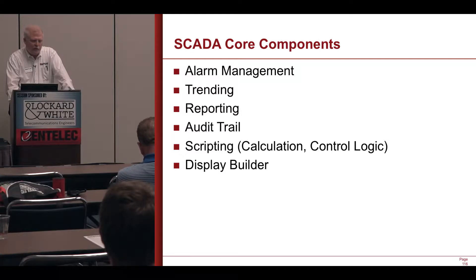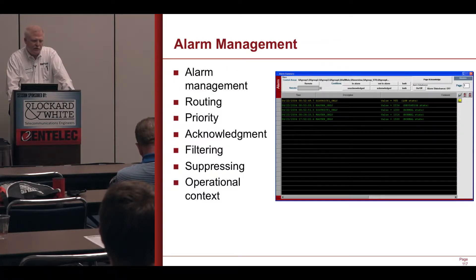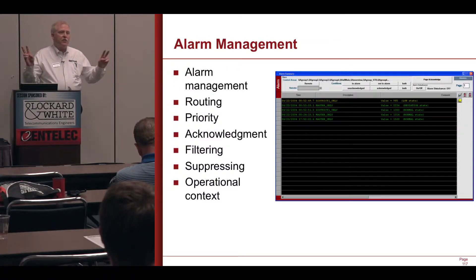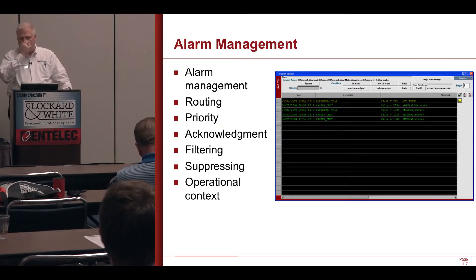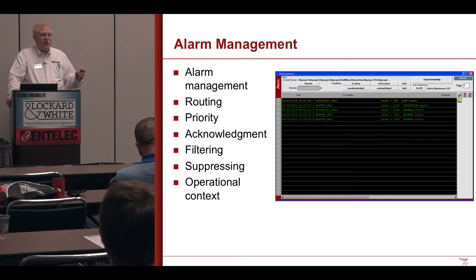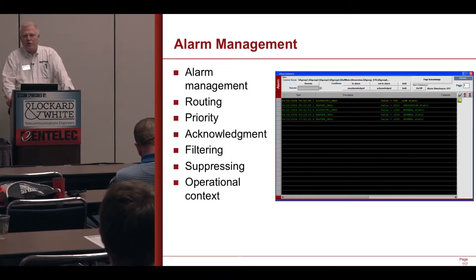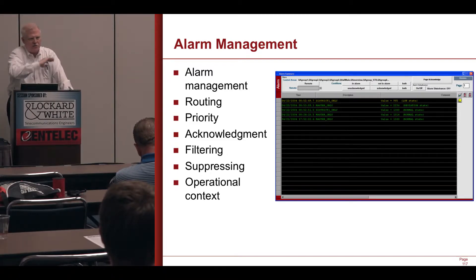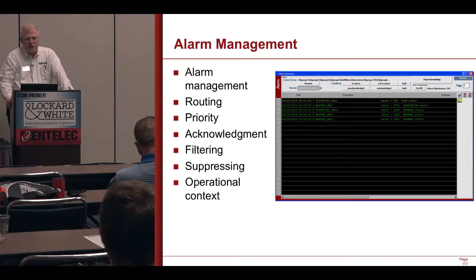We also need alarming. One of the new requirements in the regulatory requirements is alarm management. To do alarm management I've got to be able to route, set priorities, acknowledge alarms, and log all that out. I need to filter so that only the alarms for this console go to this console, and only the alarms for that console go to the other console. And I need to be able to get alarms by operating context — so if I've got 15 alarms at a site, tell me what's the highest priority alarm at that site.